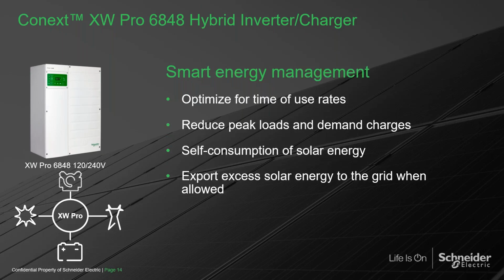Smart management: if you're in an area with time-of-use rates, or looking to do peak shaving, you can program the XW Pro to do that. Certain places have high demand charges if you go over a certain kilowatt usage, and we can inject battery power to offset grid power so you don't hit those peak demand charges.